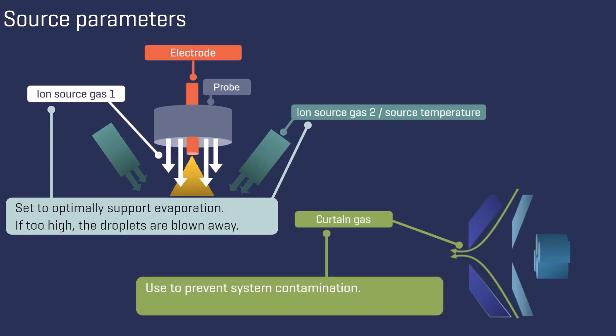The curtain gas is an important parameter that prevents system contamination. It should be set as high as possible without significant loss of sensitivity.